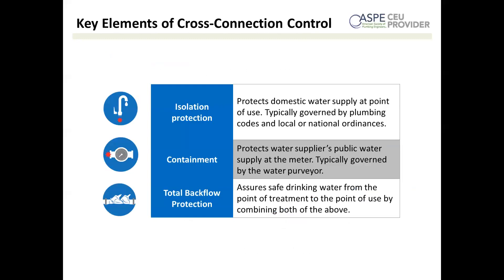What are the key elements of a cross-connection control program? The first is isolation. Isolation protects any cross-connection within the owner's premises through the use of appropriate backflow prevention devices, isolating any hazard to that particular location and protecting the remainder of the potable water system from contamination. Isolation protects you from the hazards within your own building or property, and is typically governed by Uniform Plumbing Code or International Plumbing Code.